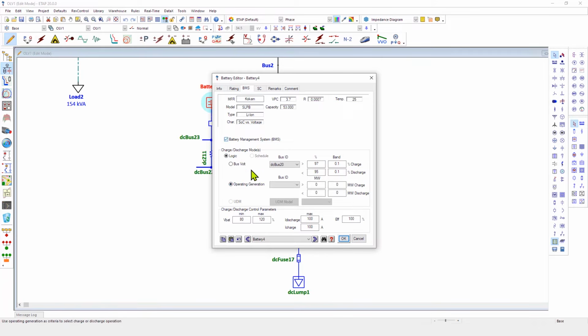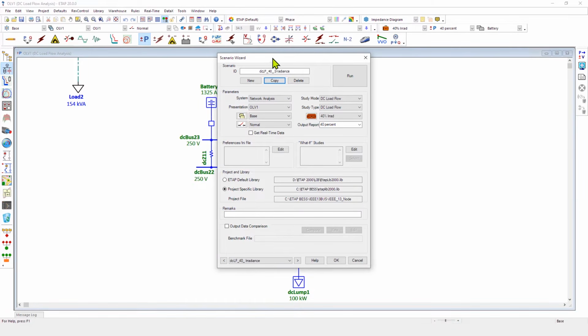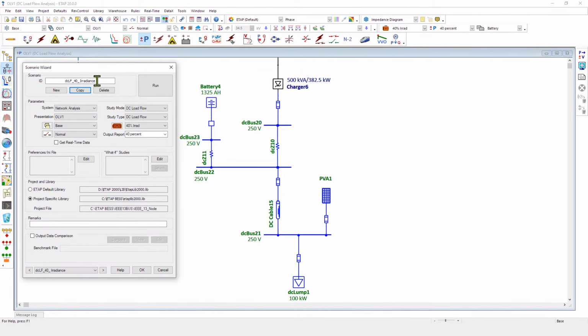You can also set the BMS to operate based on operating generation, which once again observes the power flow in a particular branch, such as a cable or a line or a transformer, to make a decision whether to charge or discharge the battery. Let's use the ETAP scenario wizard to run a couple of DC load flow cases. In these cases, we will observe what happens when the PV array power is increased from 10% irradiance to 40% irradiance, all the way up to 100% irradiance.